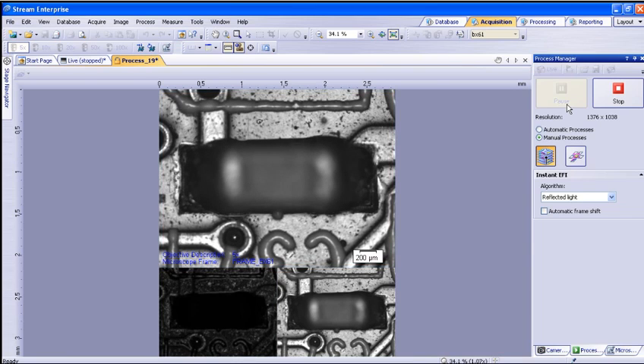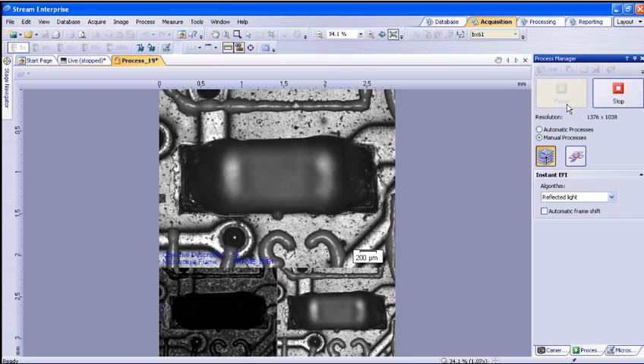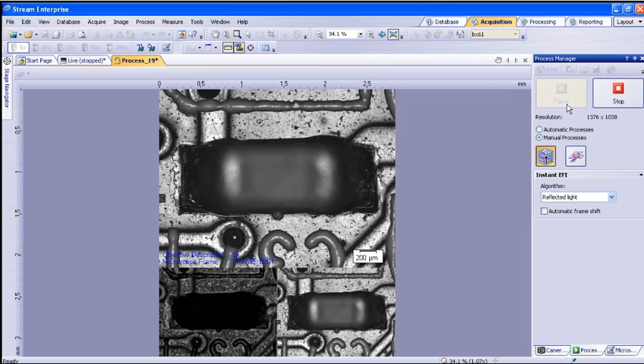Simply start adjusting the focus control on the microscope slowly to allow the software to capture the most focused pixels as you move from bottom to top of your sample's focus range. There is no time limit to complete the sequence and you can even go back through focus if there is a spot you would like to improve.